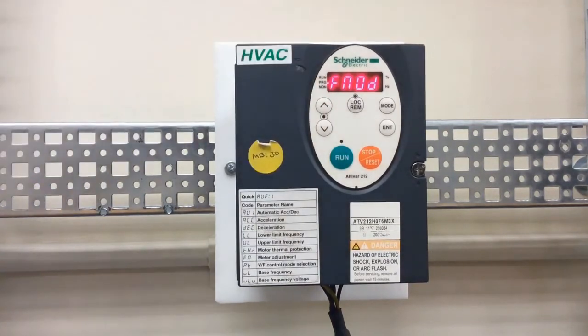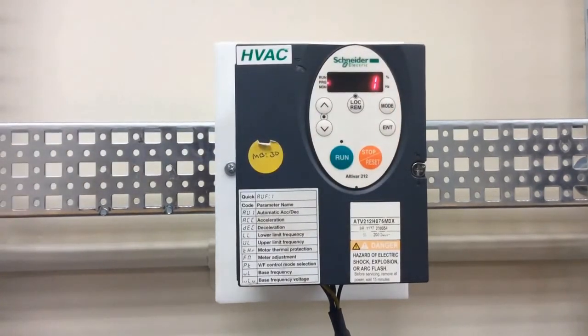The next parameter to find is FMOd, which is your frequency mode selection parameter. This tells the drive where your speed reference is coming from. To use VIA, set FMOd to a value of 1. The options are: 1 for VIA, 2 for VIB, 3 for HMI, 4 for communications, and 5 for plus or minus speed. Press enter to confirm — in this case we want 1 for VIA.